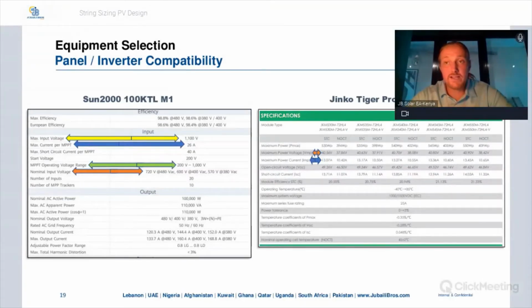Now, the Huawei C&I range of inverters is made to accept these large panels. The residential inverters are not. So those C&I inverters are fine for these large panels. The residential inverters are not. But one thing to pay attention to, if you're using a very large panel, and let's say the max power current is 15 amperes, and you look at this inverter and the max current per MPPT is 26 amperes.